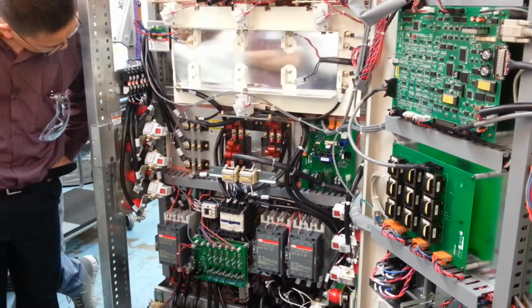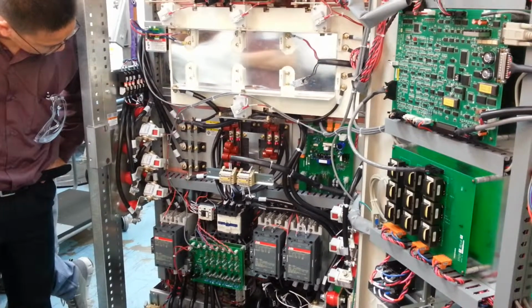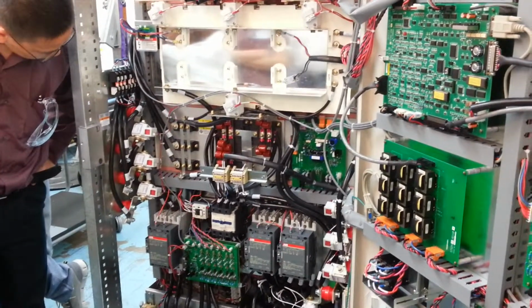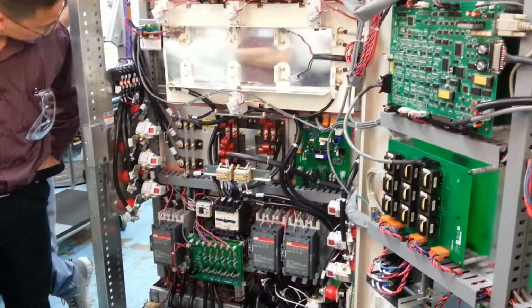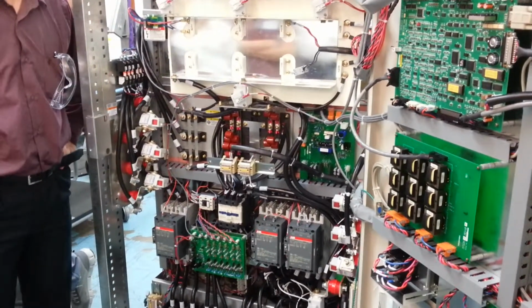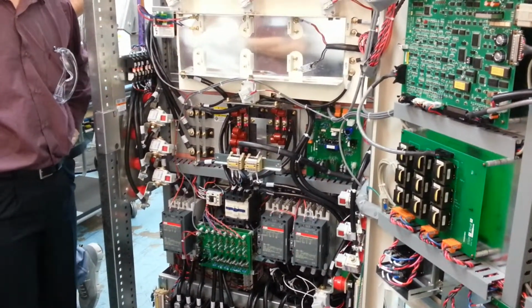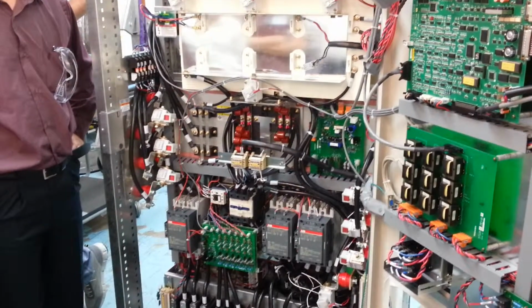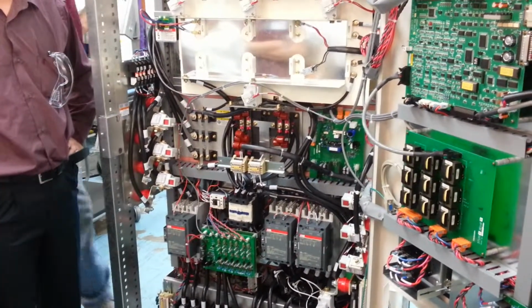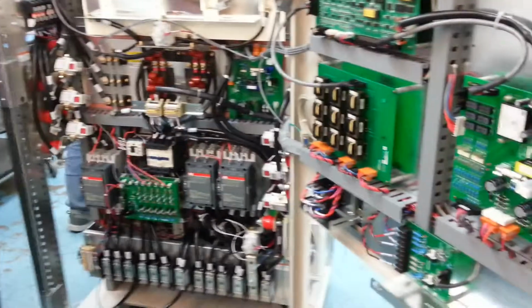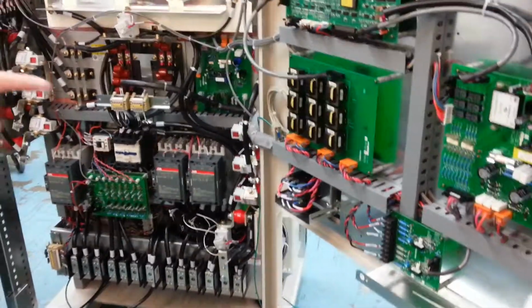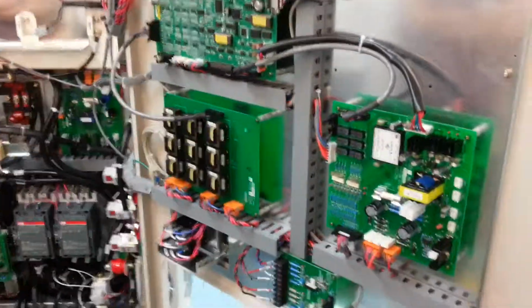On these units, since it's a rectified front end, whatever your input is, times the square root of 2, 1.44, DC bus is 680 nominal. So where is the power supply for the control power? For the control power, the power supply is right there. This one? Yeah, input power comes in here for detection. Power supply board is here.